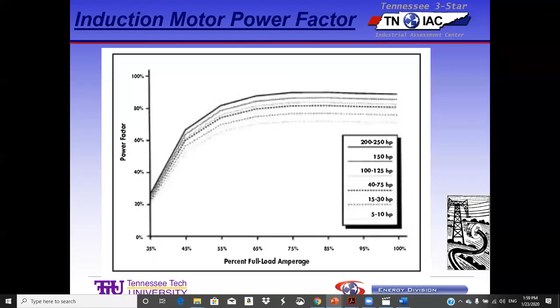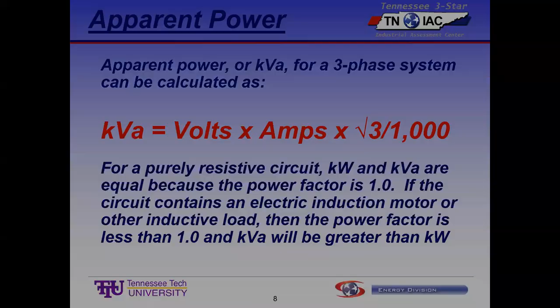All right, so we talked about that one. Oh, we're done. Okay, so if power factor is 1, kW is equal to kVA and we'll show the equation in a second. The equation for power factor is kW divided by kVA. So if kW divided by kVA is 1, kW equals kVA. And there you go. Okay, so this is the power triangle. This is kind of where the rubber meets the road. You can pretty well understand this, I think.